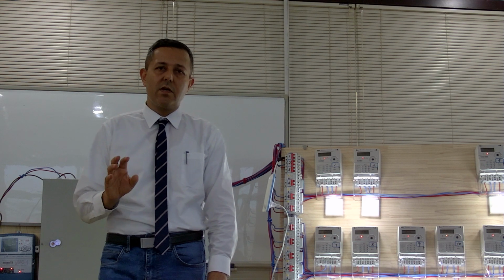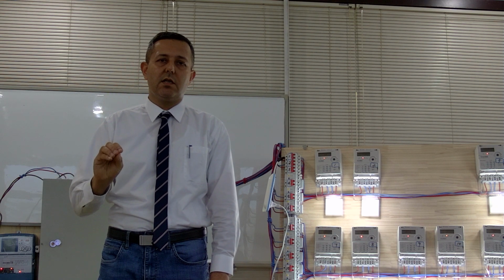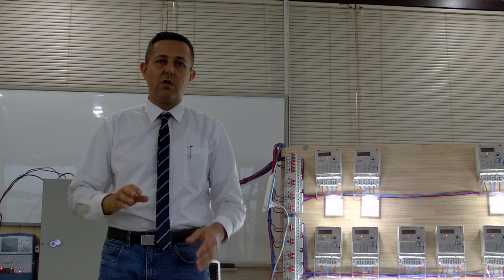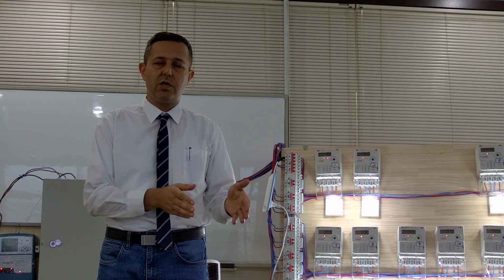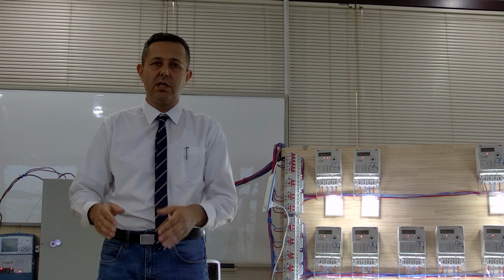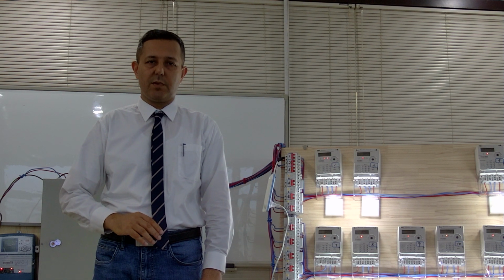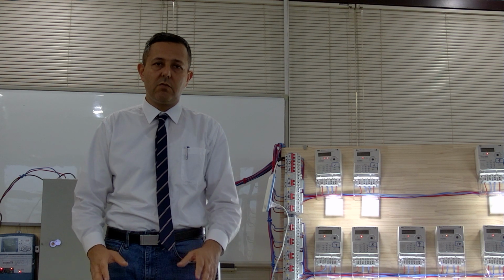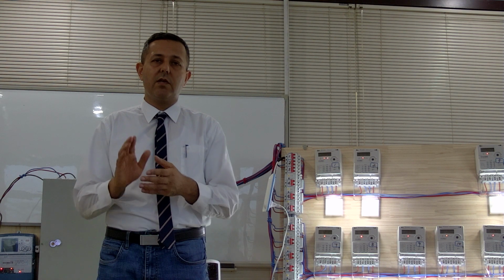So the MDR software can show you which customers are suspected to use miners, or which customers claimed to be residential but are actually using electricity for industrial purposes. Based on the pattern, the harmonics, and the reactive power and power factor measured from the customer premises, we can determine the type of customer and show a report of which customer is using which kind of equipment.